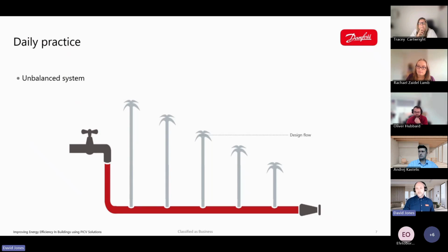In order to understand how an unbalanced system looks, we can use this basic but effective visual of a hose with holes in it connected to a tap. The hole in the middle is our design flow we're trying to achieve. As you can see, the tap provides flow, but because water takes the path of least resistance, we have too high a flow rate at the first hole. We have too high a flow here, and insufficient flow towards the end of the run, at the hole furthest away.